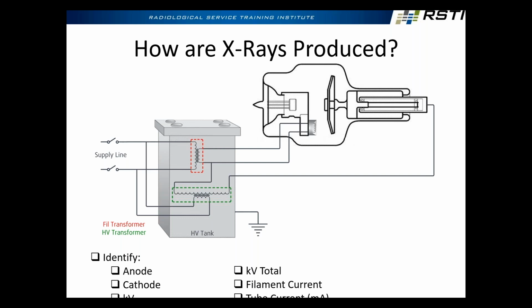Tungsten, atomic number 74, very, very high atomic number, which makes it an excellent target material for the production of X-rays. And it also has the highest melting point of any of the naturally occurring elemental metals, over 3,422 degrees Celsius, which is like 6,192 degrees Fahrenheit, something like that. Which seems like, oh my God, over 6,000 degrees, there's no way we could ever possibly melt that. We can melt it in one exposure, because we have generators out there that are capable of up to 100 kilowatts of output. And especially if something happens and our anode isn't rotating, oh yeah, we'll melt it right quick, right?